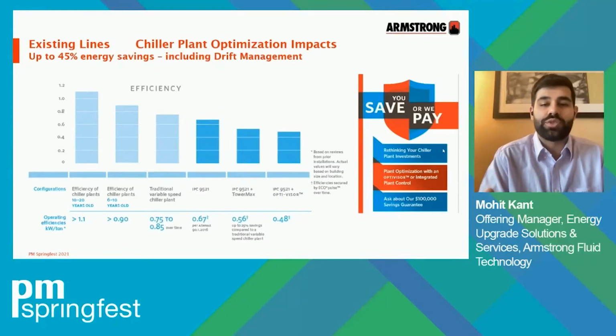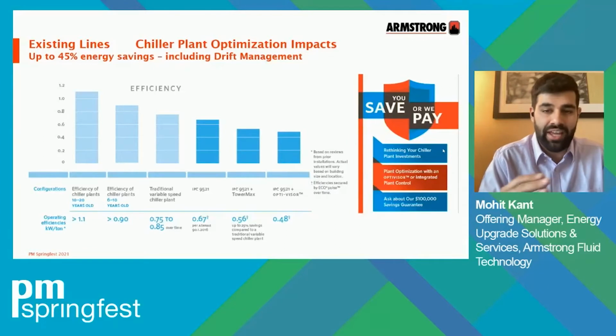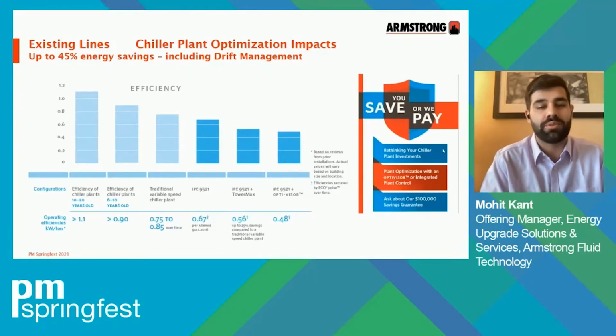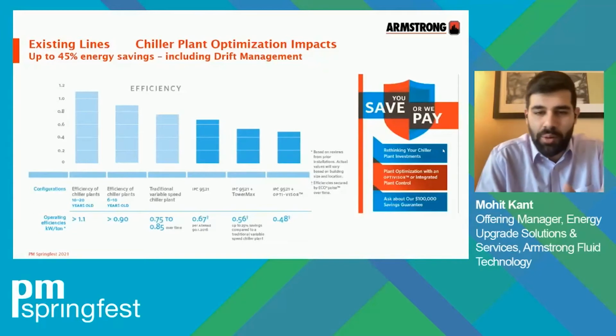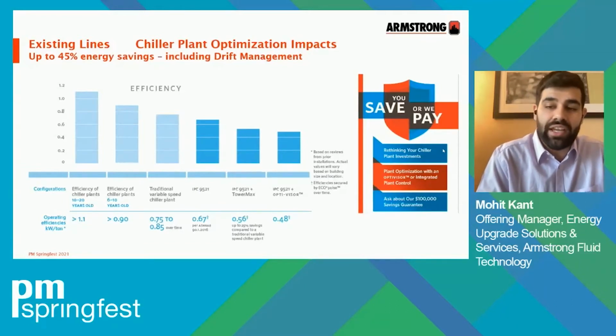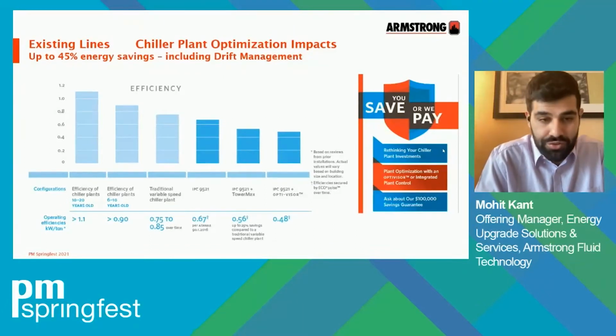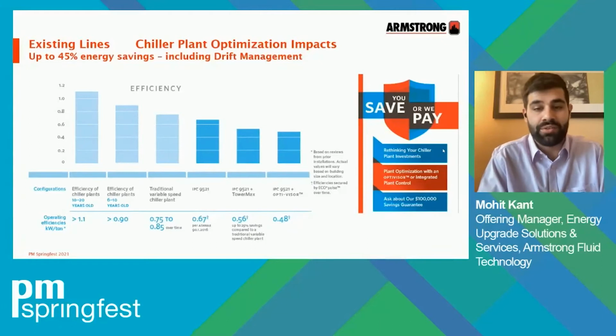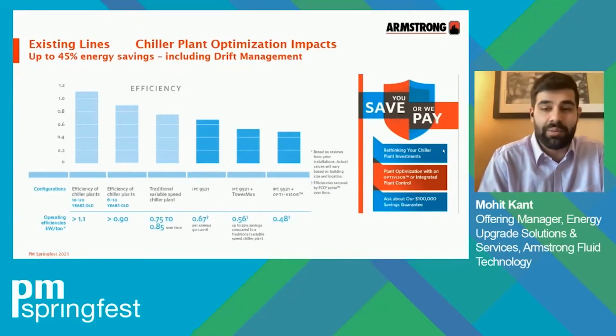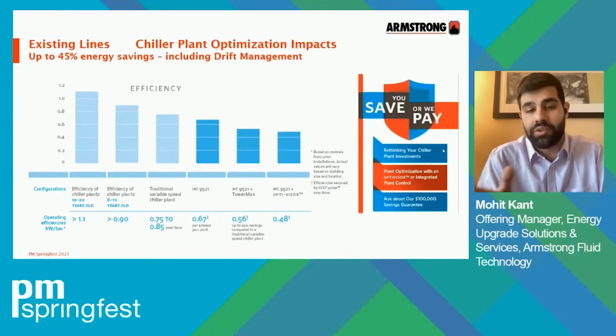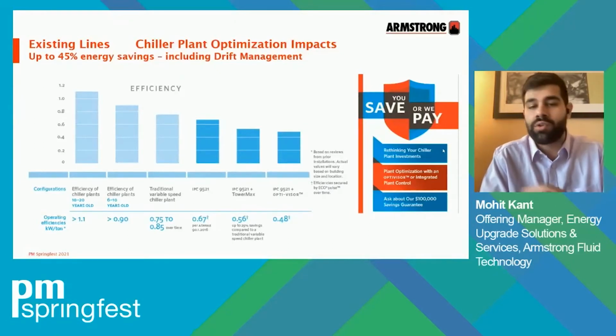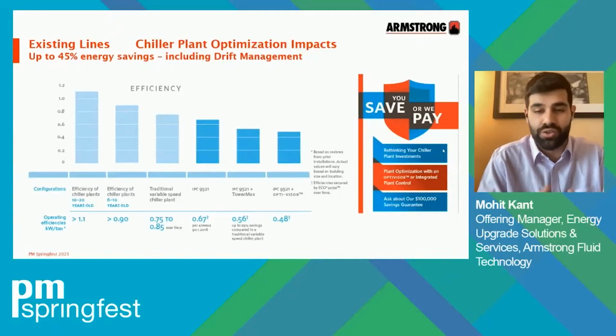This feeds into Armstrong's suite of automation and optimization solutions for your mechanical plant, developed using the flow-informed approach. While most existing mechanical plants operate at efficiencies of over 1.1 kilowatts consumed per ton of cooling delivered, Armstrong solutions can help bring it down to as low as 0.48 kilowatts per ton on average. These numbers have been confirmed using Armstrong's Active Performance Management Suite, which enables intelligent monitoring of mechanical equipment within your plant. Armstrong also has case studies from across the globe for all the solutions outlined so far on its website, armstrongfluidtechnology.com. Please help yourselves with that information as well.